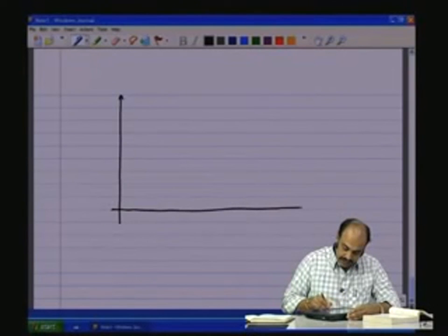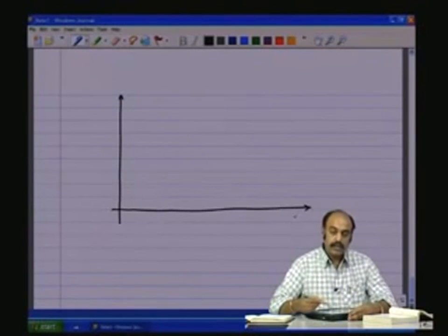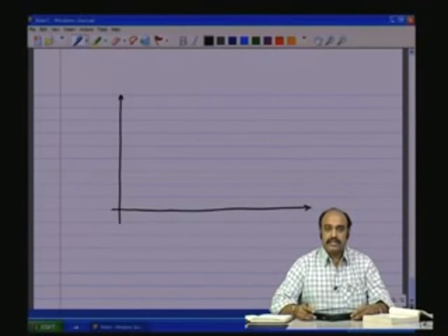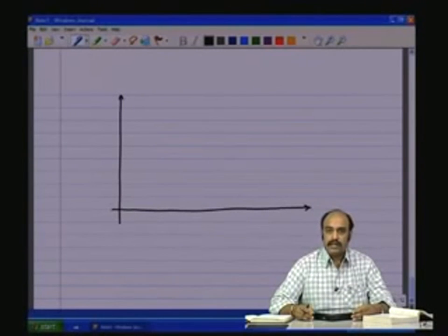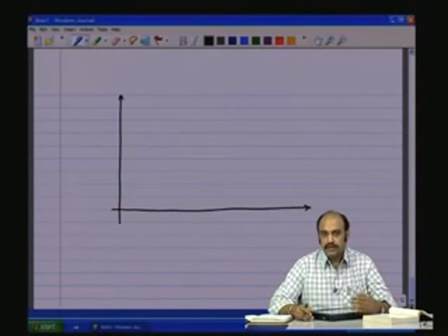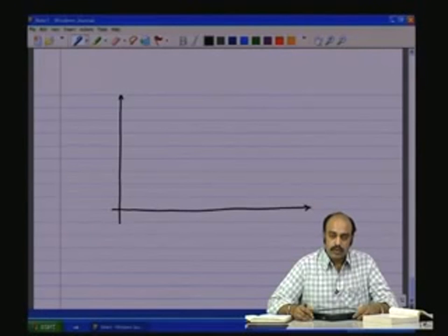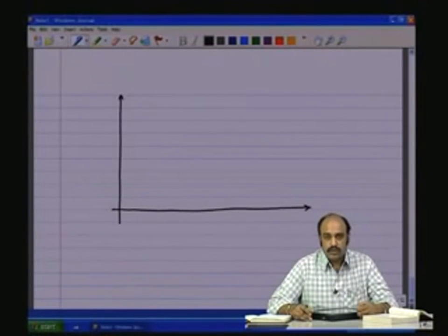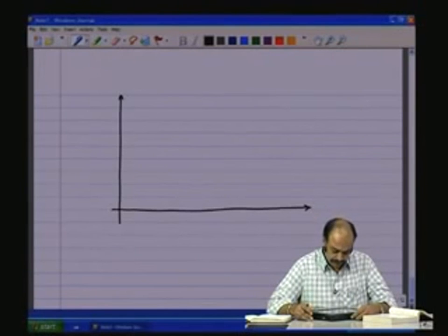The permanent magnet excitation, the separately excited excitation, the shunt excitation, then the compound excitation where you have the normal compound to take care of the loading effect on the field, then you have the over compound to take care of the loading effect on the field, plus also the loading effect of the armature winding resistance on the output terminal voltage, and of course, the differential compound, so that you want to bring down the output voltage drastically to limit the short circuit current in some applications like DC arc welding.